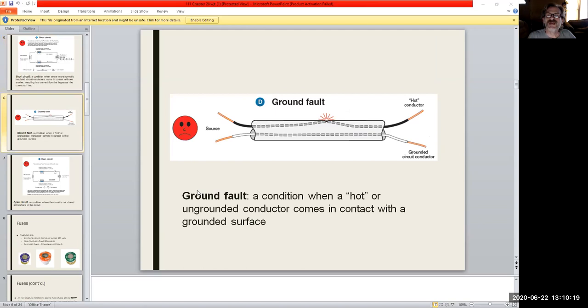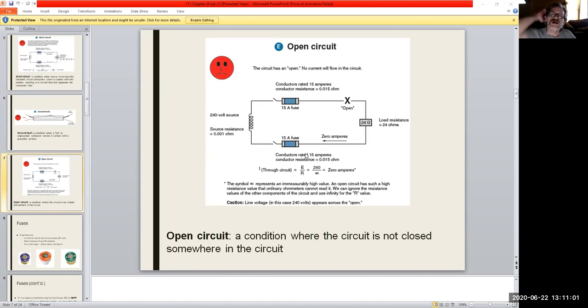Not a fun one. Then we get what they call a ground fault. So what do they mean by that? The definition says it's a condition when a hot or ungrounded conductor, in this case our black line here, comes in contact with a grounded surface. What this is illustrating is a pipe like EMT, so it's metallic. You had a break in the insulation, and the pipe will be grounded, so when this conductor makes contact with that pipe, it basically creates a ground fault, if you will. It can happen in a few different ways, but anyway.